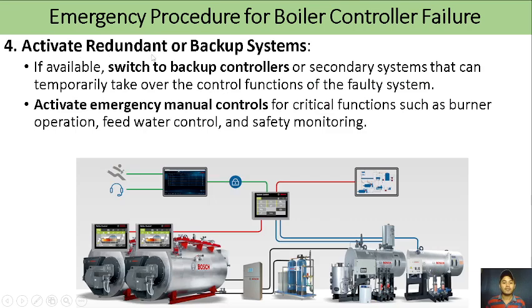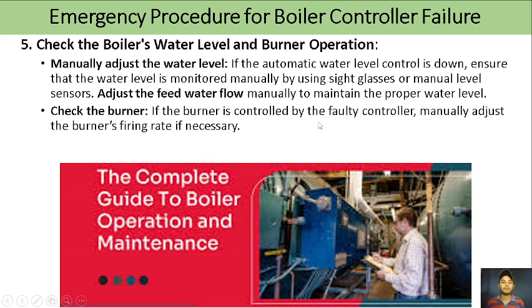And then activate redundant or backup system if there is. If you have a backup system, switch to backup controls or secondary system that can temporarily take over the control functions of the faulty system. So activate emergency manual controls for critical functions such as burner operation, feed water control, and safety monitoring. Check the boiler's water level and burner operation. Manually adjust the water level, adjust the feed water flow, and check the burner. So manually adjust the burner's firing rate if necessary.